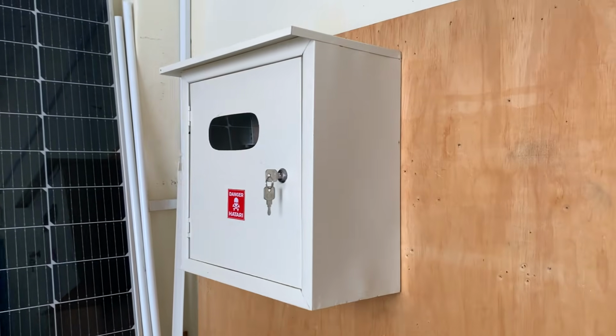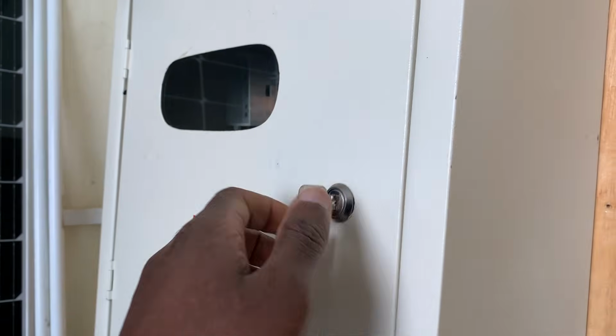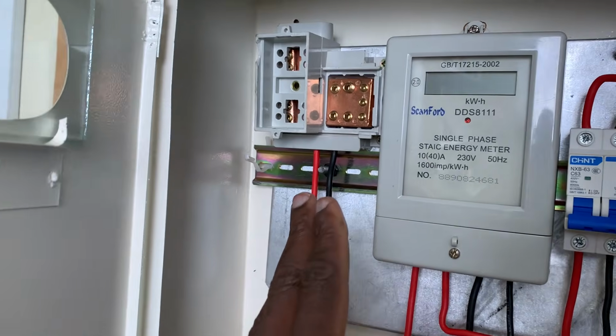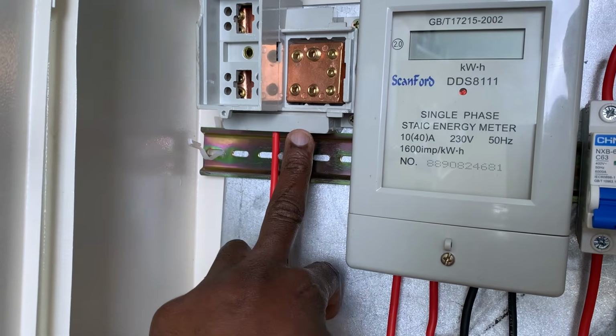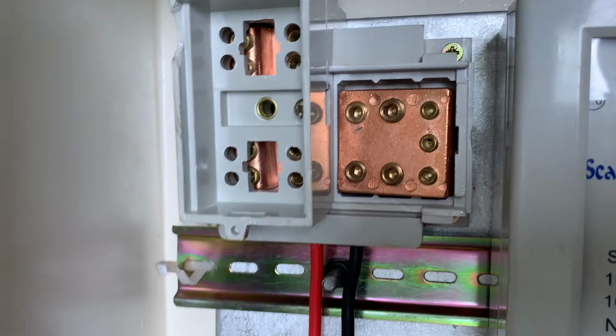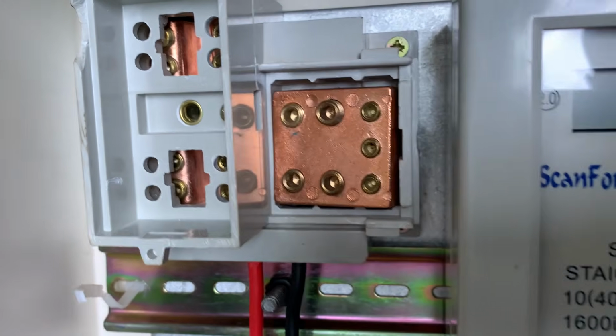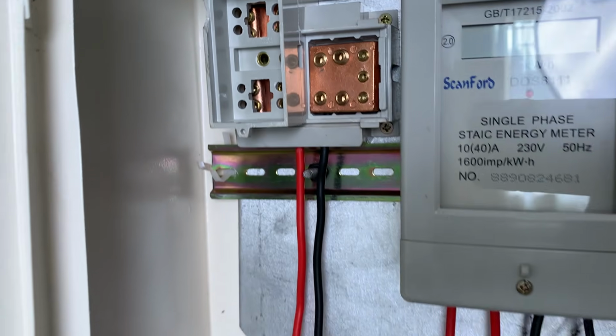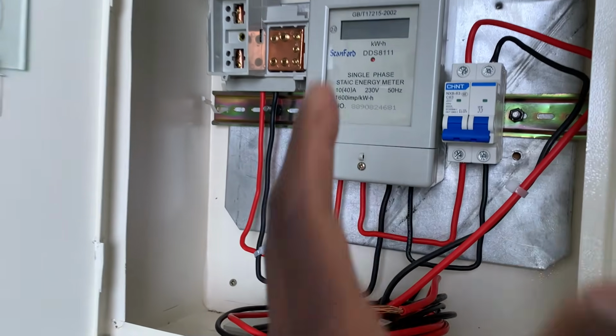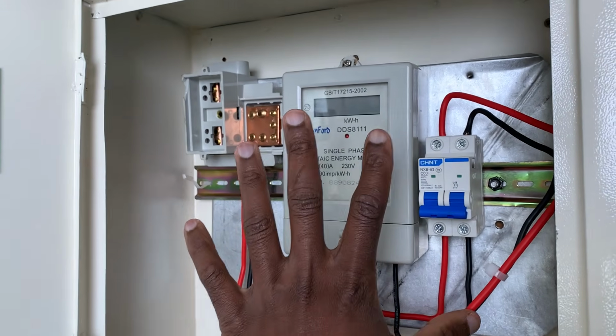But again, my top bosses, today let us emphasize on something very important when it comes to earthing, which is on the meter board. We were discussing connecting the earthing at this point, meaning bonding the earthing as well as the neutral. But that is overtaken with time because of the type of meters we now have on the meter box.